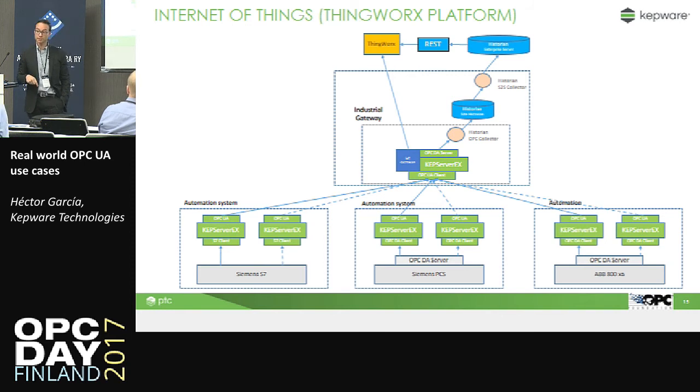And the last one I wanted to share with you is a use case of a mining company from here, from Finland. They have 14 different locations. I have shown only 3 of them here, just to show you that we used KEPServerEX to communicate directly with the Siemens devices, the Siemens PLCs, using Kepware's driver, but in other plants, they already had their systems up and running with their own SCADA systems.